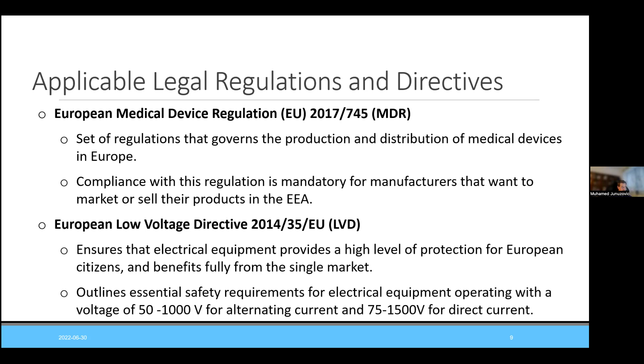It outlines essential safety requirements for electrical equipment operating with a voltage of 50 to 1000 volt for alternating current and 75 to 1500 volt for direct current. For everything above, there is a high voltage regulation. Also, very important for therapy accelerators, there is a directive for electromagnetic compatibility, which ensures that electrical and electronic equipment does not generate or is not affected by electromagnetic disturbance.